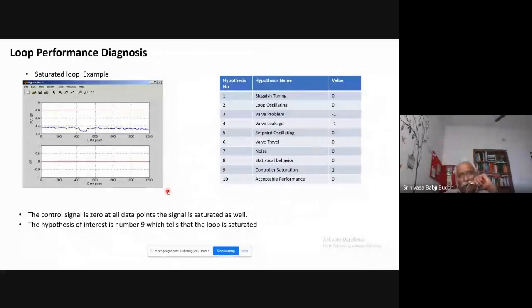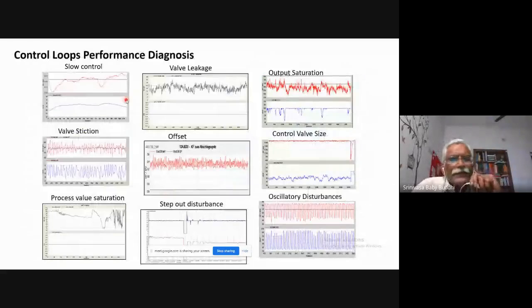Okay. So these are various examples of slow control and output saturation, valve friction. When we have a valve friction problem, there is a particular type of behavior in the process signals. And this is oscillatory disturbances. Control valve sizing: you can see here most of the time the control valve output is close to 100. So when it is close to 100, if there is some disturbance, it will not be able to act on the control error because of the limitation of the control valve size. Okay, which leads to undesirable control performance.